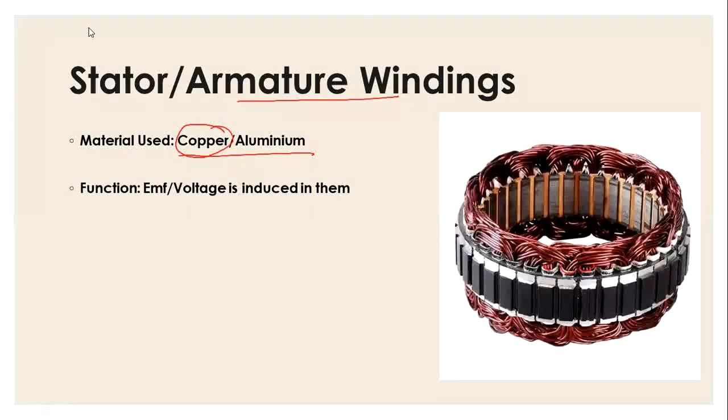And what is its function? The function of the stator winding is to produce the EMF or the voltage. So basically, the three-phase voltage is induced in these stator windings, and from the stator windings we take the three-phase power as the output power. These are the components of the stator, that is, the stator frame, stator core, and the stator winding.